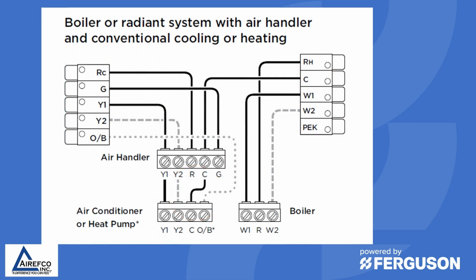You'll also see on some thermostat hookups that you will have an RC connection and an RH connection. These are usually done, like in this example, on a boiler or radiant system with an air handler and conventional cooling or heating, to keep the power from the air conditioner or heat pump separate from the boiler power.